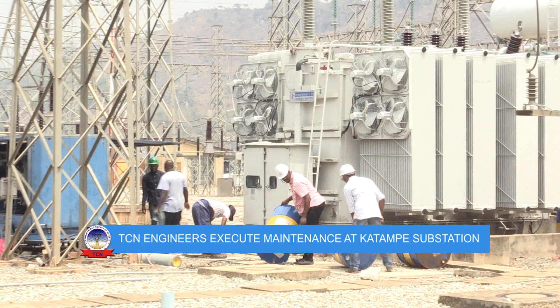All this process is toward energizing the new installation transformer. The procedure has been taken so far. Even since last week, we have booked for the outage in advance at the ISO. The maintenance crew also checked the oil compartment and the transformer base as they injected oil into the brand new power transformer.